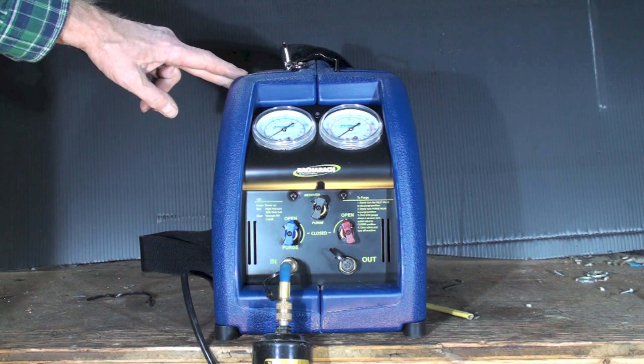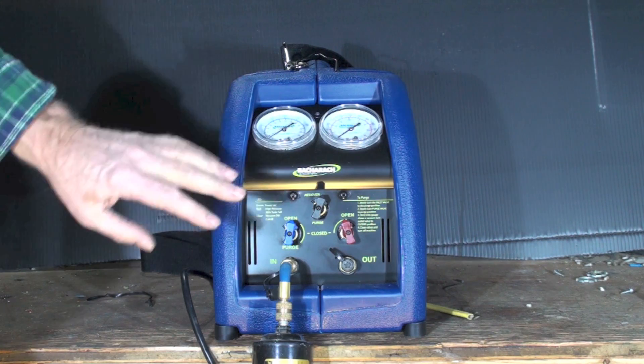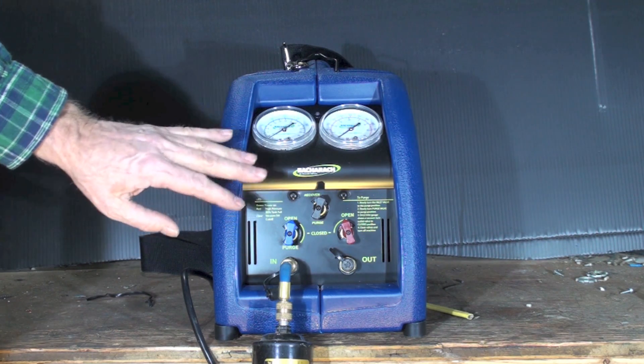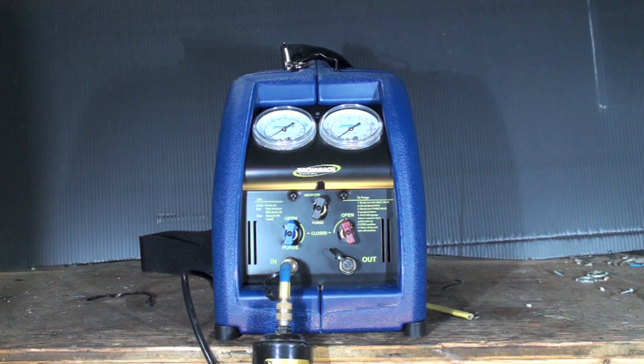This machine pretty much takes care of itself. It's pretty hard to destroy these things except for the liquid issue. If it over-pressures, there's a pressure switch that shuts it off, and of course there's a vacuum switch that shuts off when it reaches the necessary vacuum. The next video I'll talk about on these things is how to set one up and how to pull refrigerant out of a system.